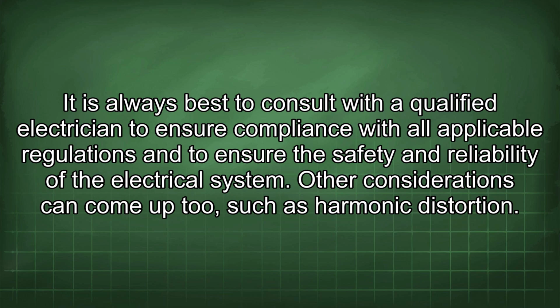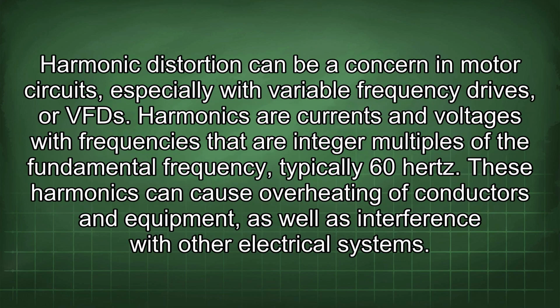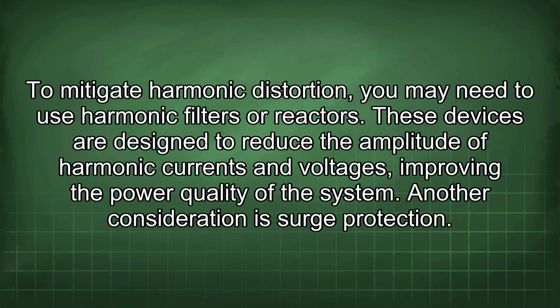Other considerations can come up too, such as harmonic distortion. Harmonic distortion can be a concern in motor circuits, especially with variable frequency drives, or VFDs. Harmonics are currents and voltages with frequencies that are integer multiples of the fundamental frequency, typically 60 Hz. These harmonics can cause overheating of conductors and equipment, as well as interference with other electrical systems. To mitigate harmonic distortion, you may need to use harmonic filters or reactors. These devices are designed to reduce the amplitude of harmonic currents and voltages, improving the power quality of the system.